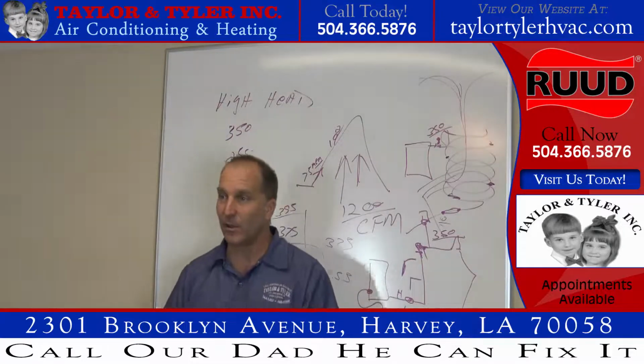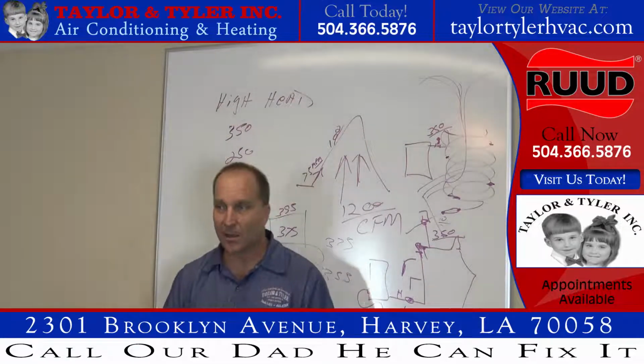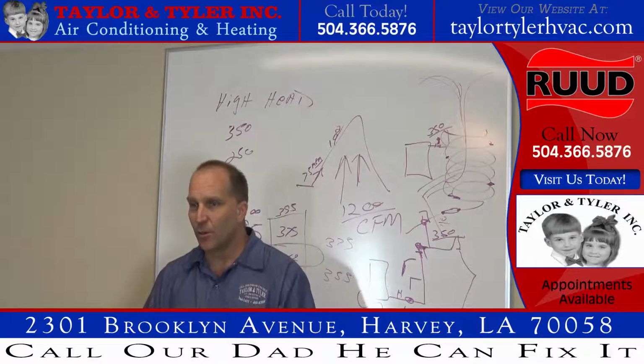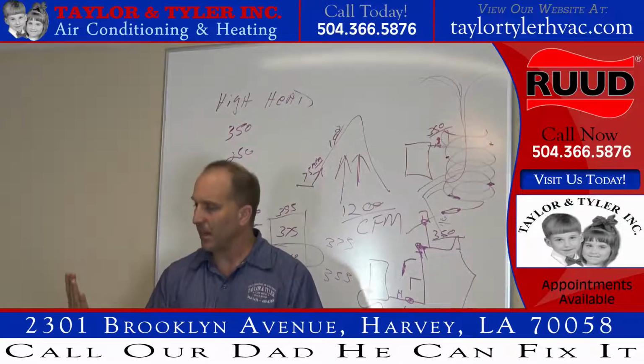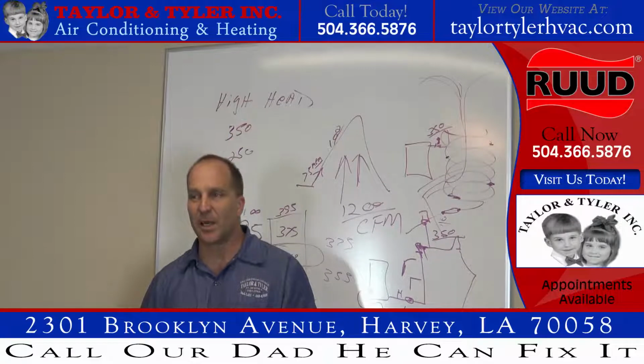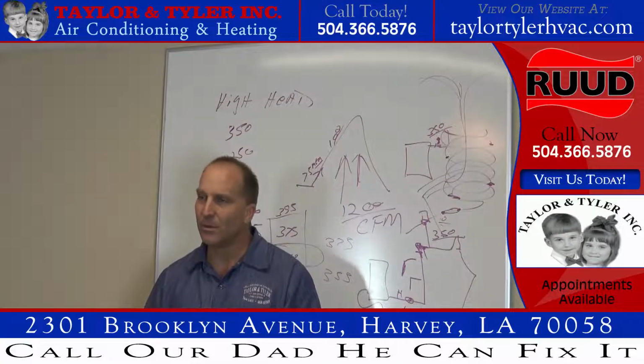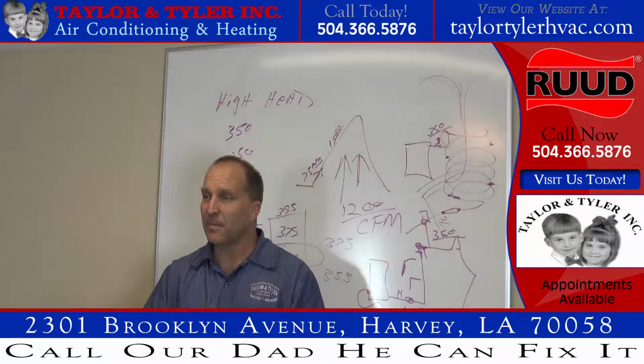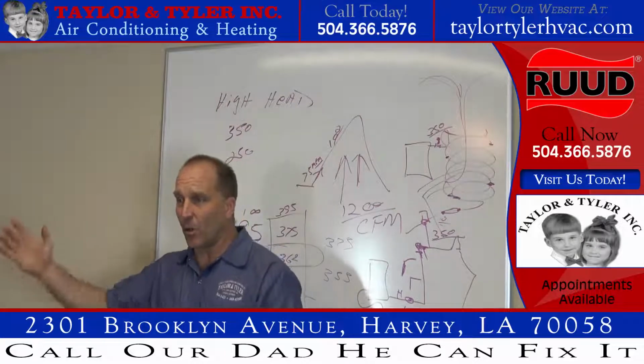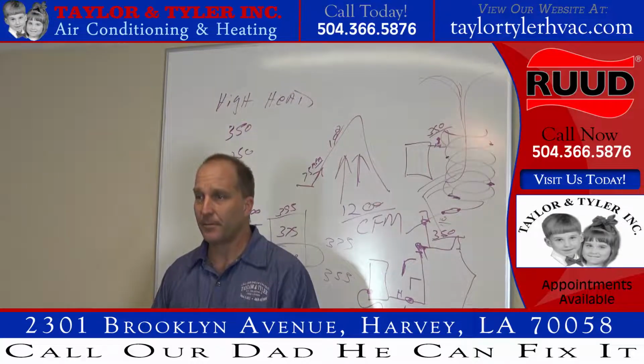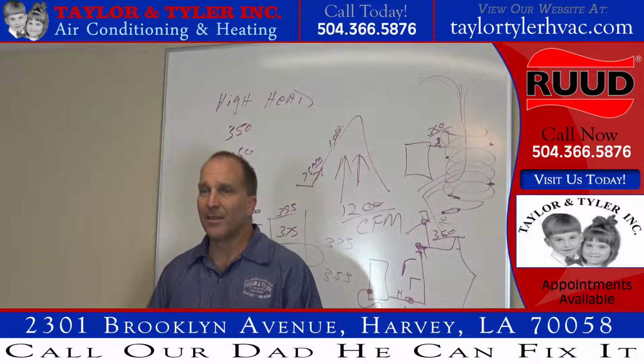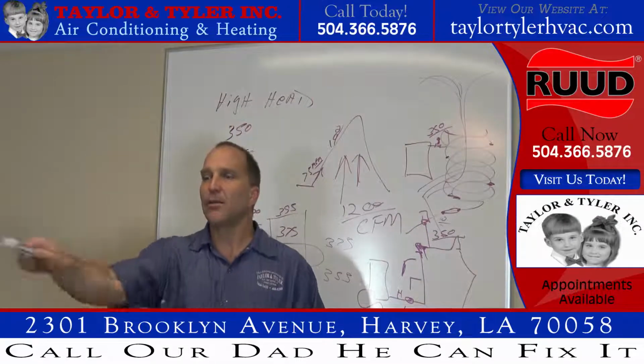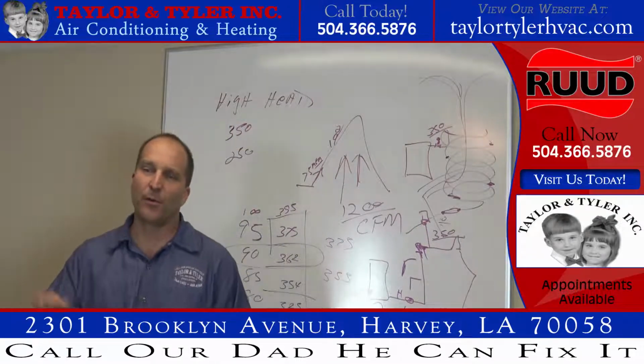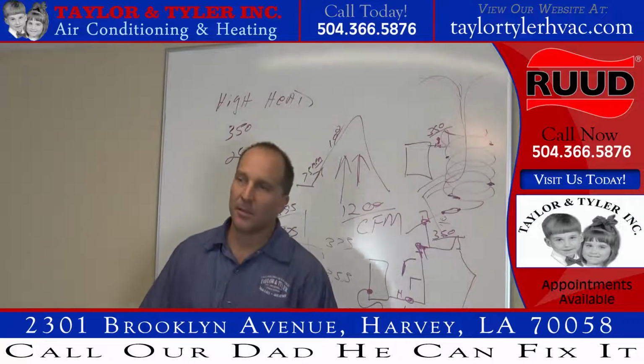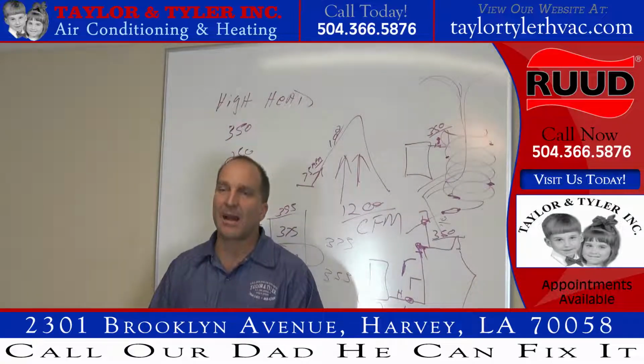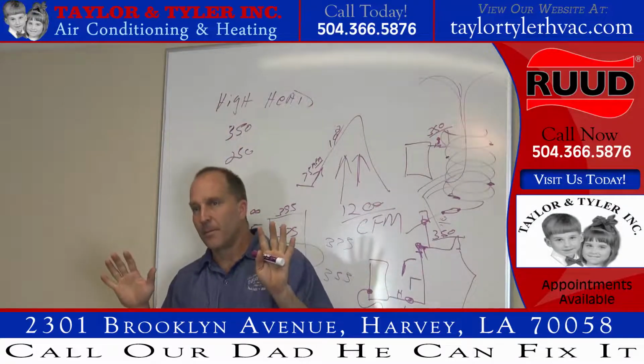Doesn't the arrow point to overcharge? Head pressure high, subcooling's high, right? So if you look at the chart, you read it and you go, it's got to be overcharged. Got a 22-degree subcooling. No. If you know what I told you the other day, if it doesn't fit every category, it's not it. Okay? So in this case, it's neither one of those. I've got a perfectly weighed-in system. Somebody kinked that line after the fact and nobody knew about it.